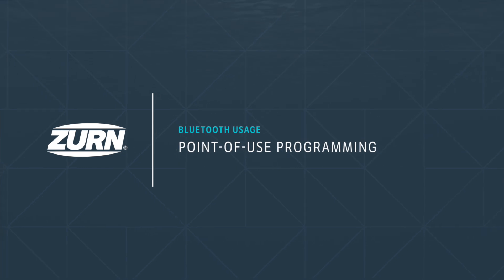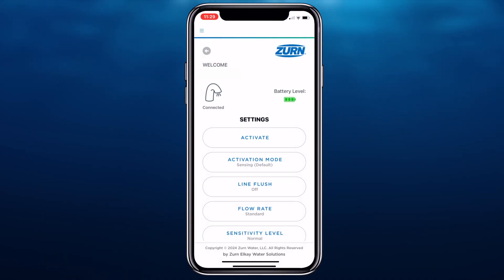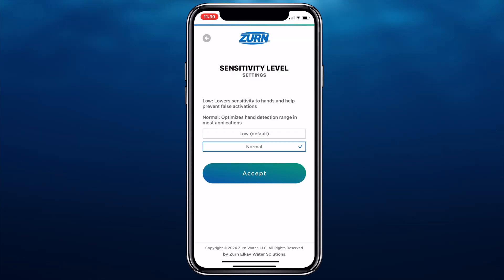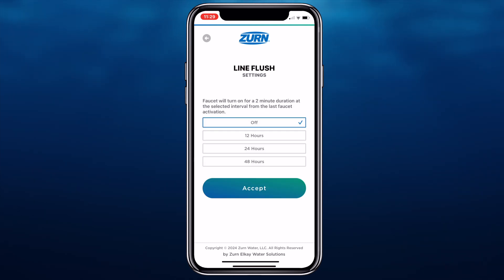Point of Use Programming. You'll find the Zurn PlumPro app is a real time saver. Through the app, you can check the faucet battery level, change the sensor sensitivity, and adjust water metering and timeout settings, all without needing to go under the sink or handle electronic components. You can even use the app to set up a regular line flushing schedule and adjust it as needed to minimize stagnation during periods of restroom inactivity or comply with thermal or chemical disinfection flush protocols.